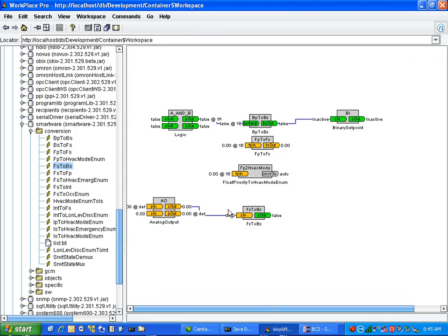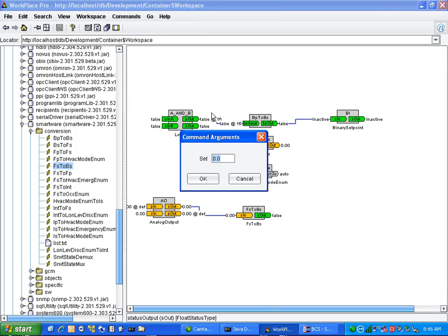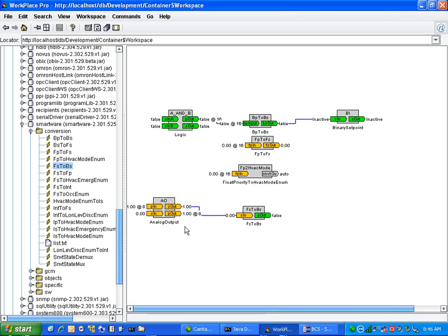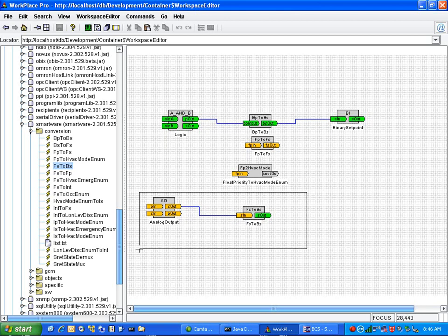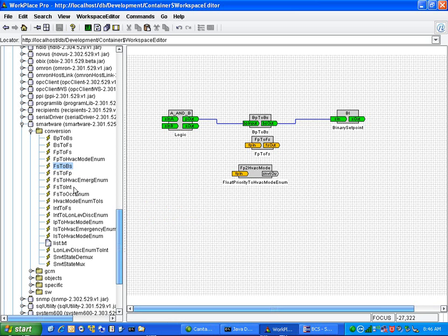I have a 0. It's giving us a false. I have an idea that, just like in Workplace Tech or in microzones, any value greater than 0 is going to be an on. And I'll bet you if I go as high as a 1 and I link that up and I send a 1, it goes to true. So that's all it's saying, just like in all of our programming logic: any value greater than 0 is an on, a true, and anything 0 or less, in the negatives, is going to be a false. Clean that out of there.